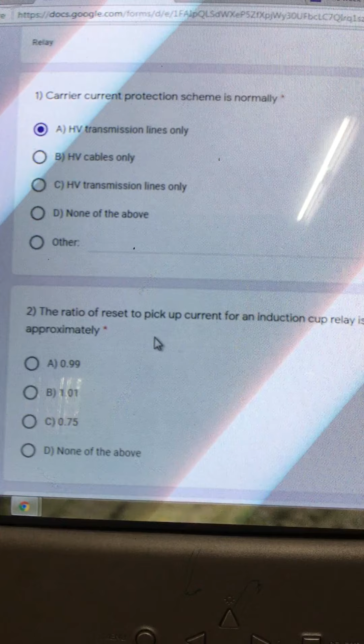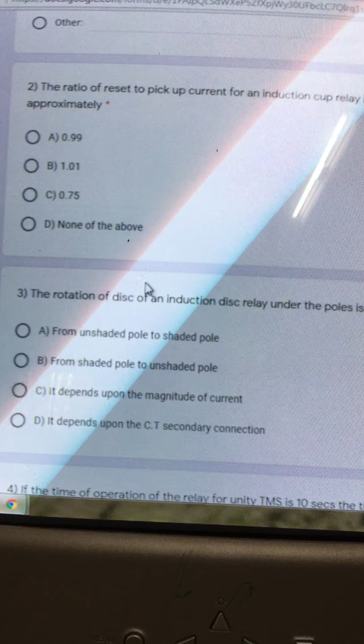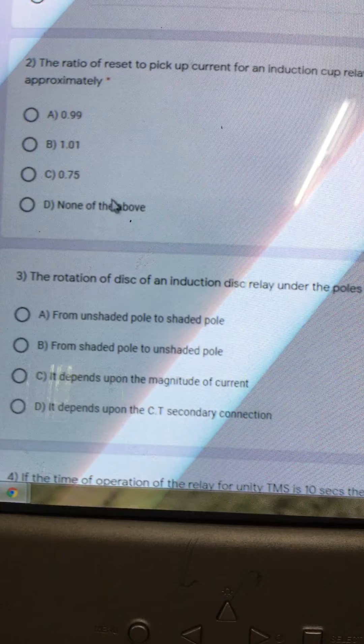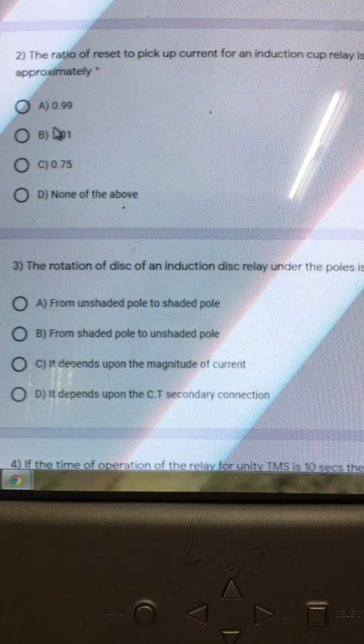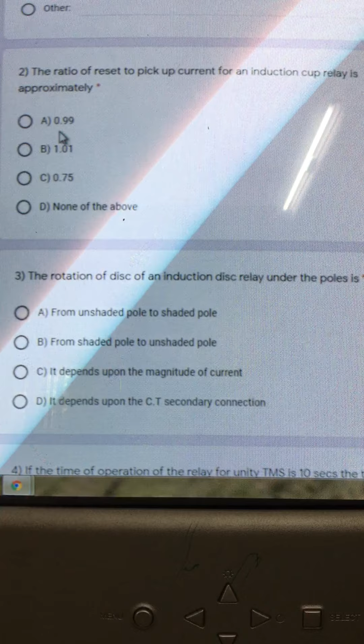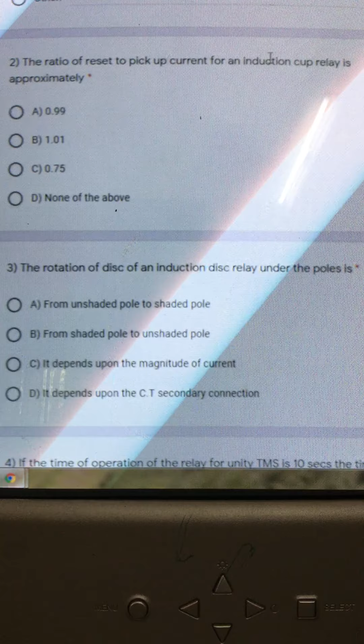And the second question. Second question is the ratio of reset to pickup current for an induction cup relay is approximately. So the induction cup relay ratio of reset to pickup current value. The induction cup relay has the principle similar to that of split phase induction motor. And like any other electromagnetic relay, the induction cup relay does not depend upon the air gap or the magnetic circuit, right? It depends only upon the control spring torque.